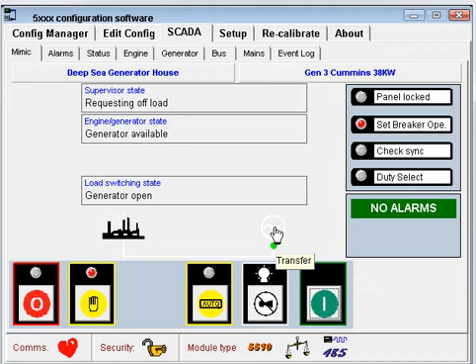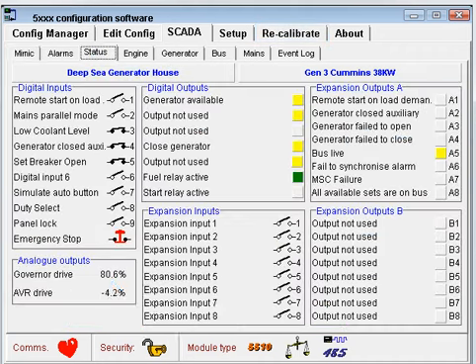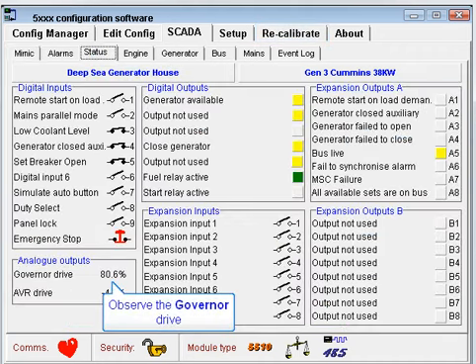Now visit the status page to check that the governor drive is around 80%. Change SW2 for the governor to fine trim this percentage if necessary.